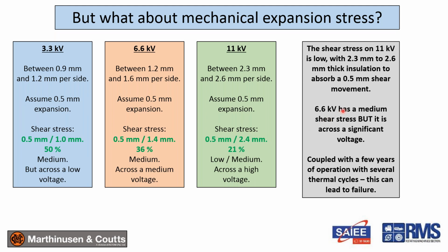So what we found is, as I mentioned, on 6.6 kV stators from several OEMs, good OEMs that don't experience failures often. And these were all in the range of 2 to sort of 5 years. And in all those cases, we found that the 6.6 kV insulation was in this region here. And we proposed in many cases to actually decrease the copper size and increase the main insulation thickness. And we don't find the same in 3.3, and we don't find the same in 11 kV.